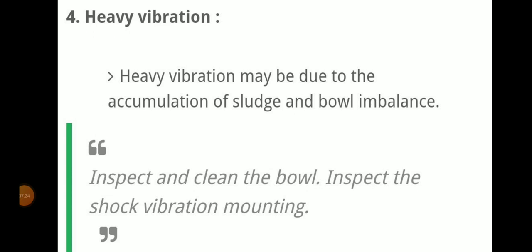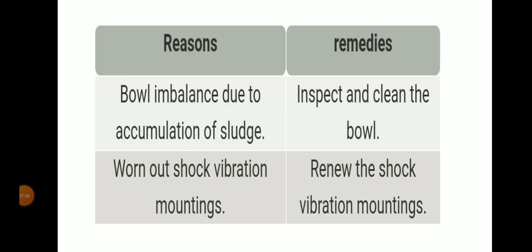Heavy vibration may be due to accumulation of sludge and bowl imbalance. Inspect and clean the bowl. Inspect the shock vibration mountings. Reason means bowl imbalance due to accumulation of sludge. Remedies means inspect and clean the bowl. Worn out shock vibration mountings means renew the shock vibration mountings.